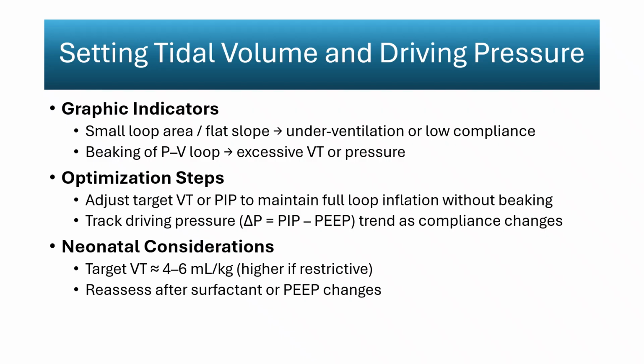In contrast, the development of a sharp peak at the top of the loop signifies that the ventilator is pushing beyond the optimal inflation point, creating overdistension with each breath. To optimize support, tidal volume or peak inspiratory pressure is adjusted to achieve full, smooth inflation without creating that overdistension peak. Because neonatal compliance can change rapidly, driving pressure becomes an important trend marker. As compliance improves, the difference between peak inspiratory pressure and PEEP decreases, and failure to adjust settings may result in unnecessarily large tidal volumes despite stable displayed numbers.